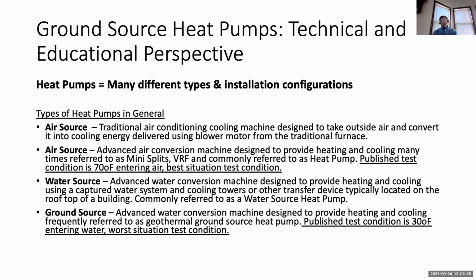The seasonally adjusted energy efficiency ratio and the COPs for an air source heat pump are tested in the best possible condition, meaning 70-degree entering air, compared to a ground source heat pump, which is tested in the worst possible condition. This is the published data people sometimes use for comparison, and when they do, you need to be clear that you're not looking at apples to apples.